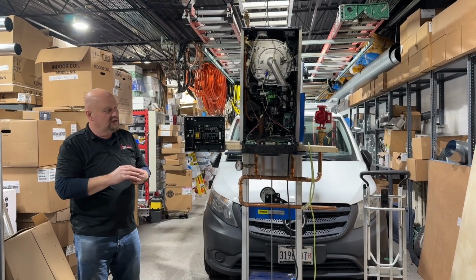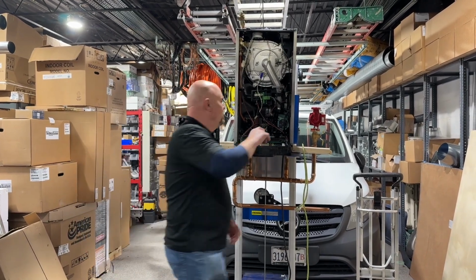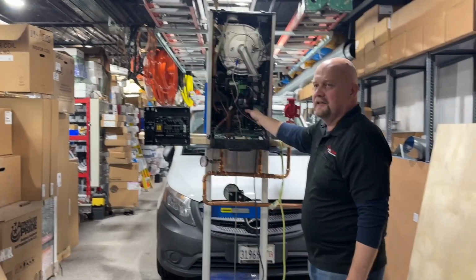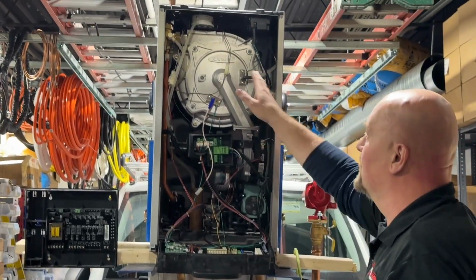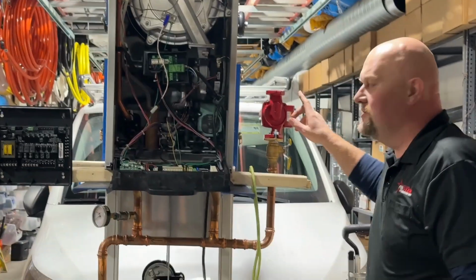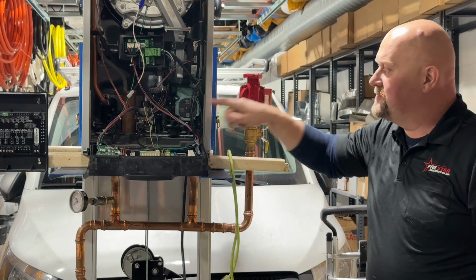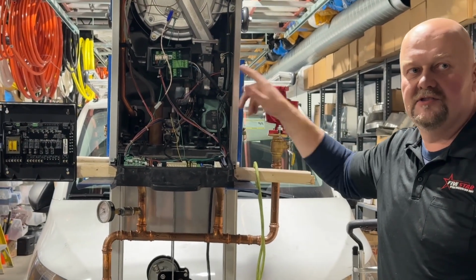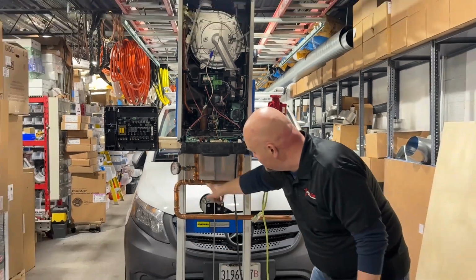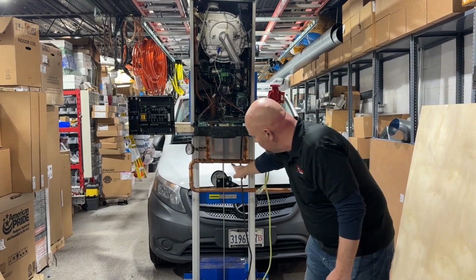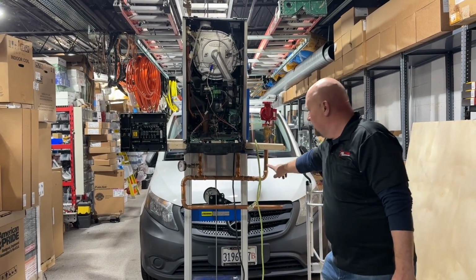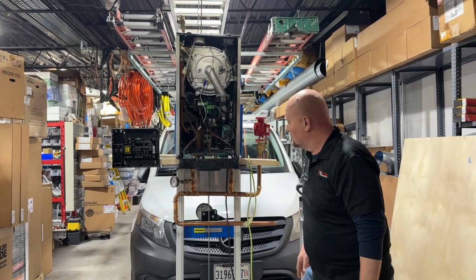But the important thing to remember is this: the new boilers will have a pump inside. That pump is there to circulate the water throughout the boiler. There always needs to be an additional pump outside. This pump is not enough to heat the house. It's only for this circuit. This circuit goes through here, mixes the water, and mixes some of the cool water returning, right?